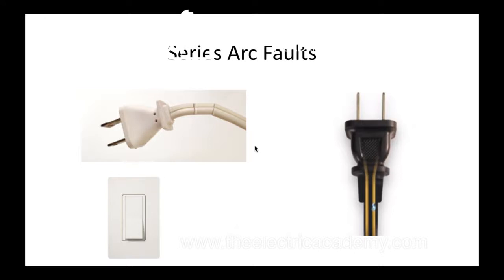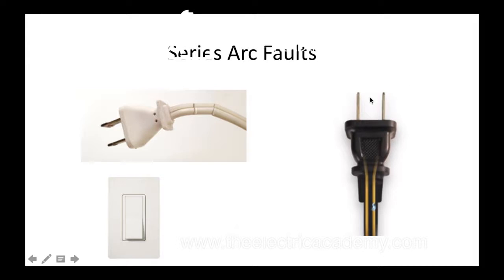A series arc fault is where you see a break in the line and there's an arc across it, so the current is being pushed across there. Series arc faults are not as dangerous as parallel arc faults, but they can still cause issues with the insulation heating up, getting burnt, and causing other issues. They still can cause a fire, but they are limited — the current on the arc fault itself is limited by the load.